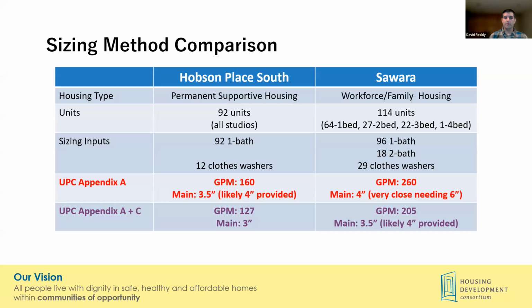The Uniform Plumbing Code has some appendices, including one that allows you to account for what are called bathroom groups. It's just a way to refine the sizing a little further and reduce your expected peak GPM, or gallons per minute, demand of water for the site. And that translates to a reduction in main size as well. Further, 3 inches for Hobson, and now we're still probably 4 inches for Sawara with that sizing method.